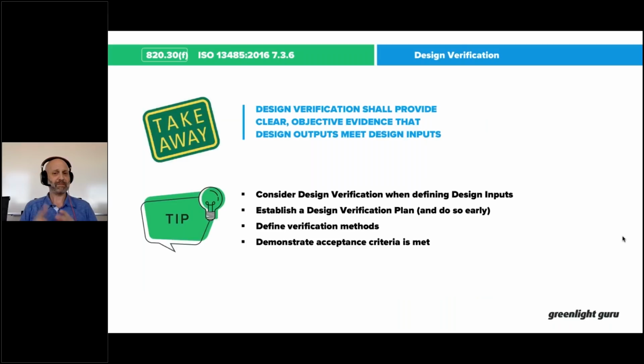So I talked about the importance of considering verification when you're defining your design inputs. I want to emphasize that again. When I'm writing design input requirements, that's a wonderful time, a great time to start to think ahead: what is it that I'm going to have to do to verify this particular requirement?